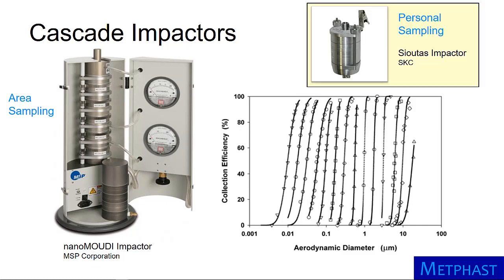However, small versions are available for personal sampling that can be operated with belt-mounted sampling pumps. These personal versions can be used for particles larger than 500 nanometers and have fewer stages and less sizing resolution than other cascade impactors such as the nanoMOUDI.